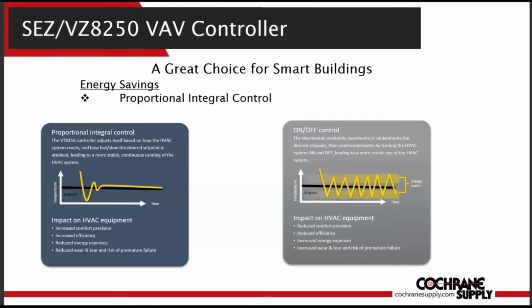The 8250 room controllers employ a proportional integral, or PI, control loop. This means that over time, the loop will tune to the space requirements, keeping the space temperatures closer to set point, reducing that overshoot. This translates into more comfortable occupants, higher efficiency, less energy usage, and less wear and tear on the mechanical equipment.